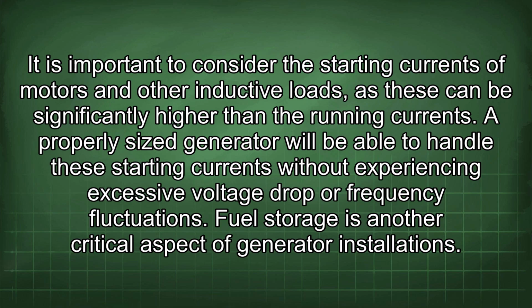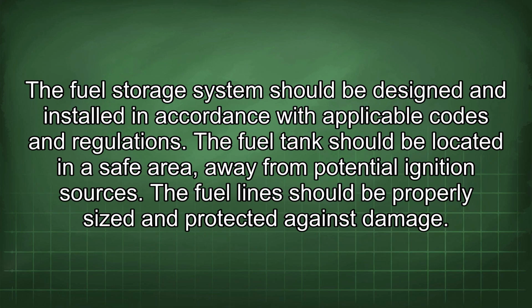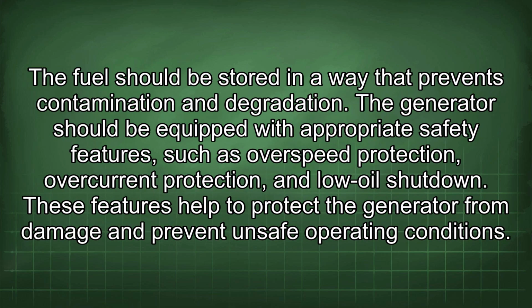Fuel storage is another critical aspect of generator installations. The fuel storage system should be designed and installed in accordance with applicable codes and regulations. The fuel tank should be located in a safe area away from potential ignition sources. The fuel line should be properly sized and protected against damage. The fuel should be stored in a way that prevents contamination and degradation.